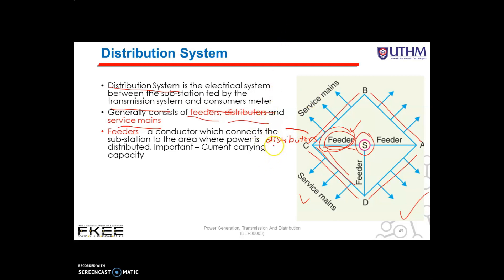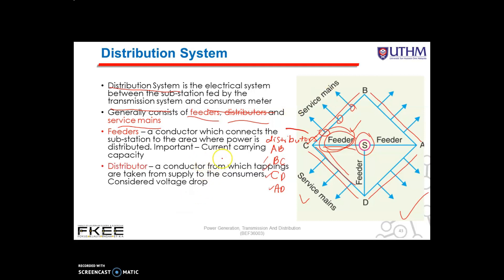We have AB, BC, CD, and AD — these are all the distributors. The current through a distributor is not constant because tapings are taken at various places along its line. While designing a distributor, voltage drop along its line is the main consideration, since the statutory limit of voltage variation is plus or minus 6% of the rated value at the consumer's terminal.